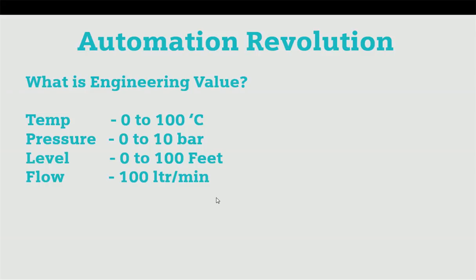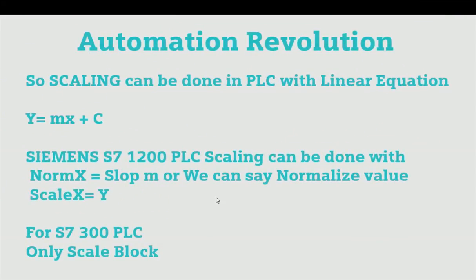Scaling is one type of linear equation: y equals mx plus c. In S7-1200 PLC, scaling can be done with two blocks: NORM_X which provides the slope, and SCALE_X which is the final output. In S7-300 PLC we use only one scaling block, but it's the same final equation: y equals mx plus c.